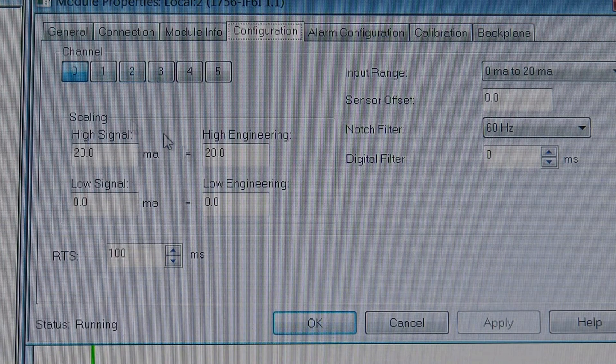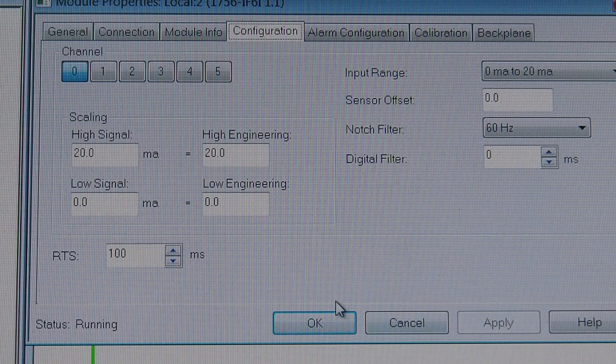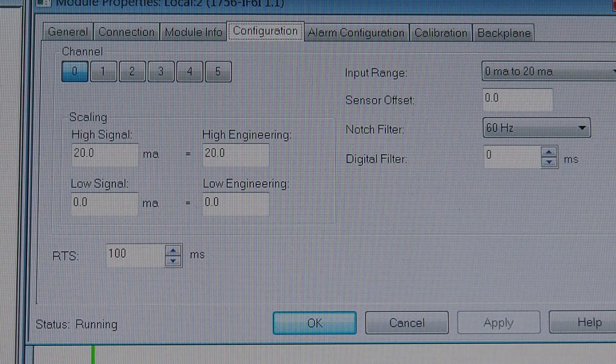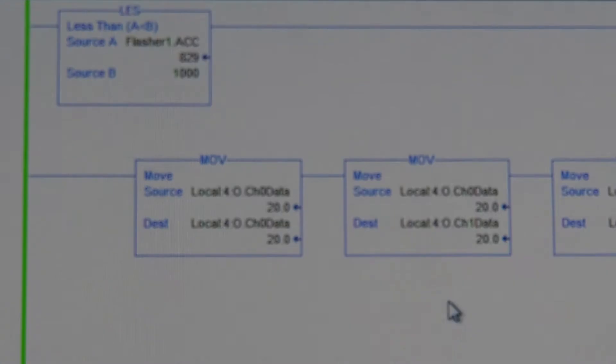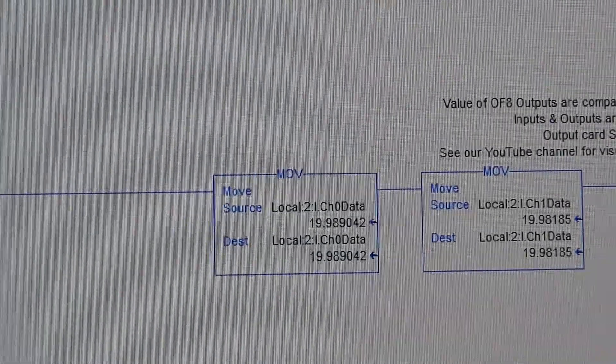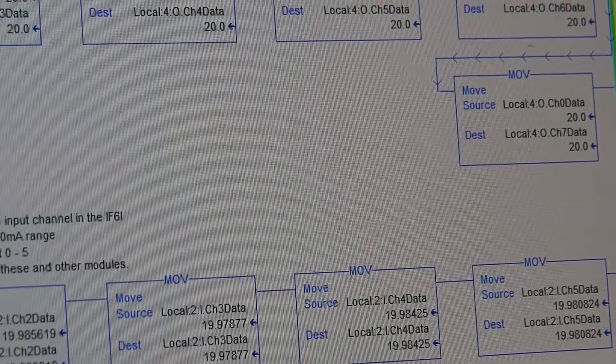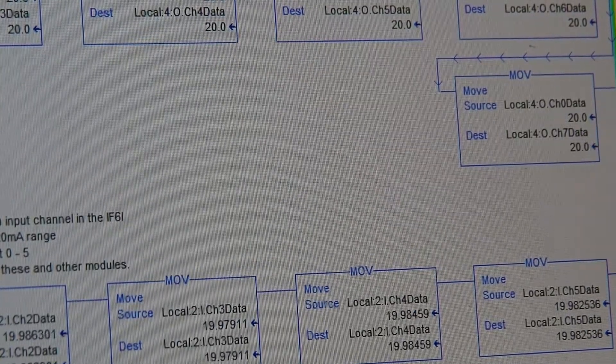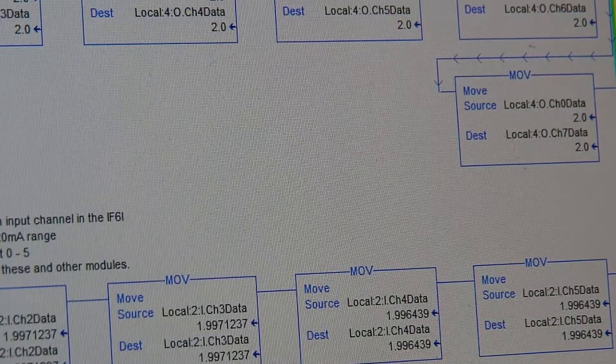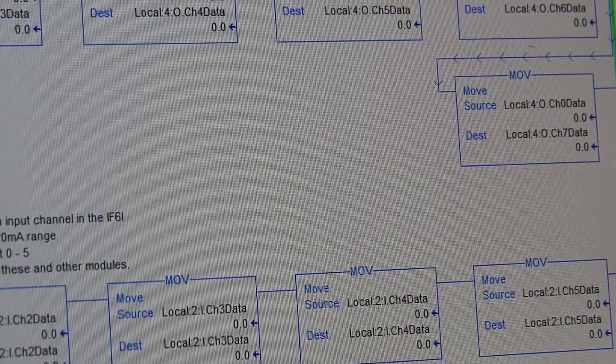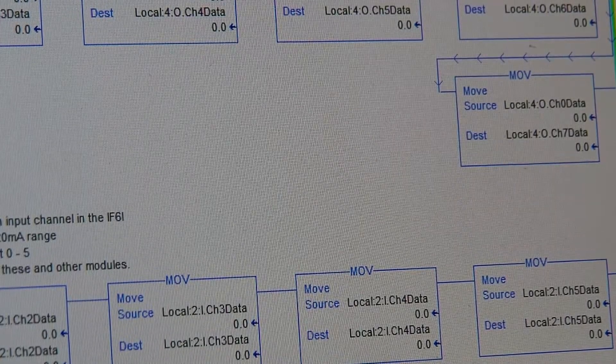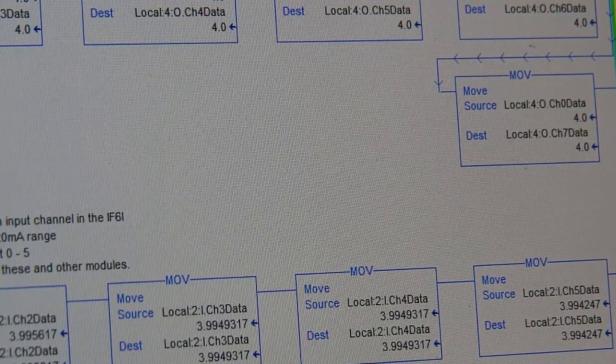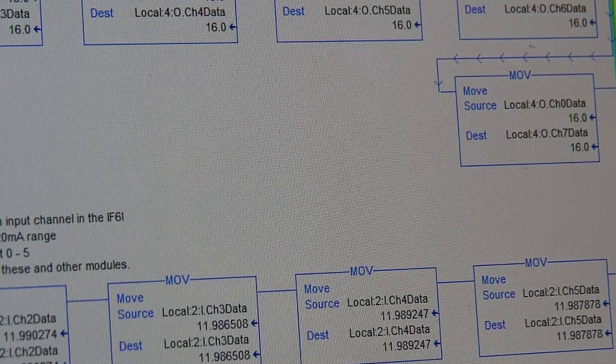So that's all there is to configuring this card. You can configure every channel individually, however you want. Voltage, current, you can mix and match on this card because it is an isolated card. And then we do the usual testing here, and currently it's at 20 milliamps. So there's our output value, there's our input values, and 0, 2. Now, 0 on milliamps stays at 0, which is unlike voltage, it'll bounce all over the place. So 2, and you can see it's a little lower than 2, but not much. 4, 6, 8, 10, etc.